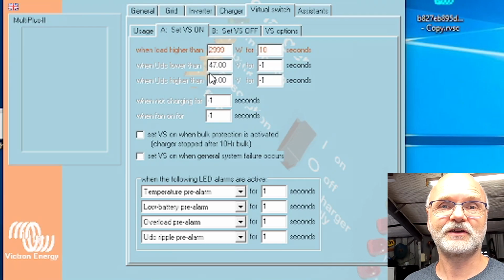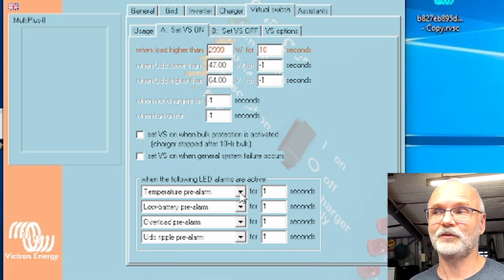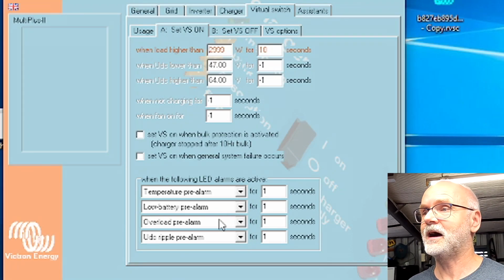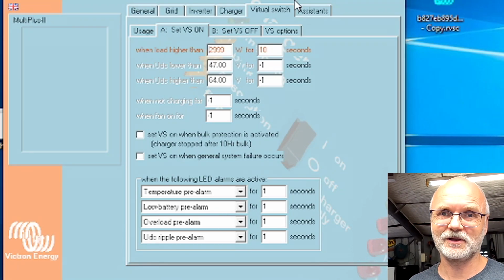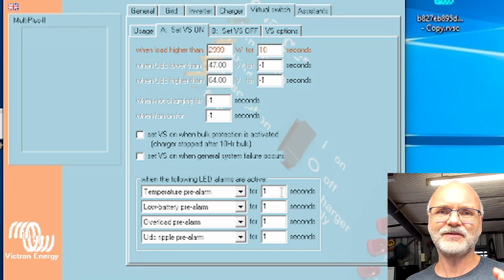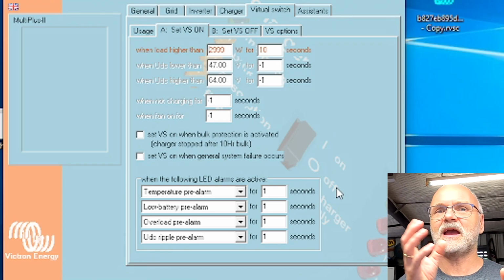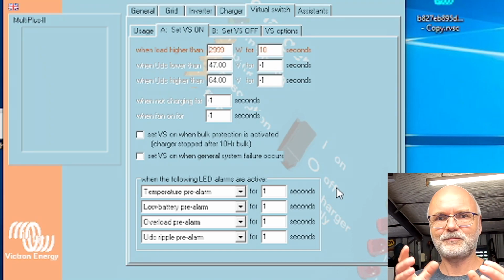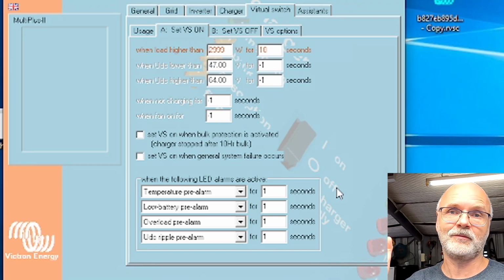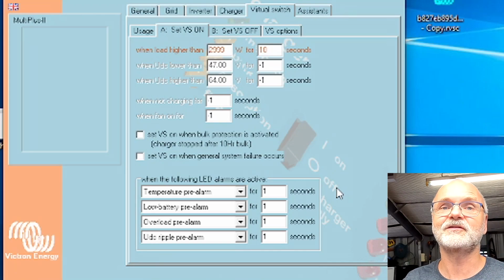For example, you can just connect an external charger to the system if your voltage of the battery gets low. We can also turn on the Phoenix if we get a temperature warning, or a low battery warning, an overload alarm, or if the DC input ripple gets too high, so the load on the inverter is very high then. And these features all make sense if you have an external power source. But because we are powering everything from the same battery, it would not make sense to do that.